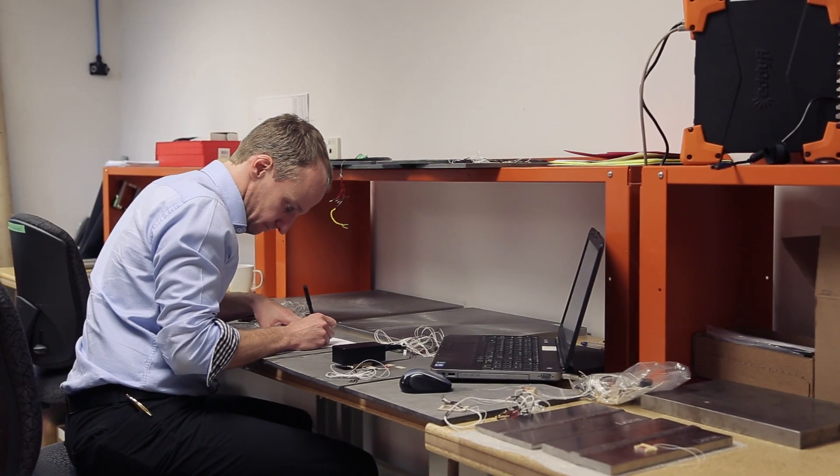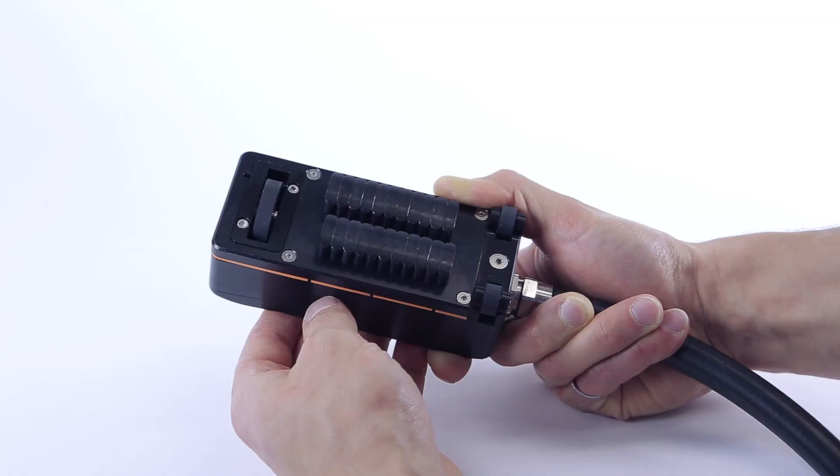The Shark probe is different, mainly due to its single-pass inspection capability. The probe monitors lift-off in real-time during the inspection. The depth of the crack is sized directly from the eddy current measurement, as taken by the coil arrangement.